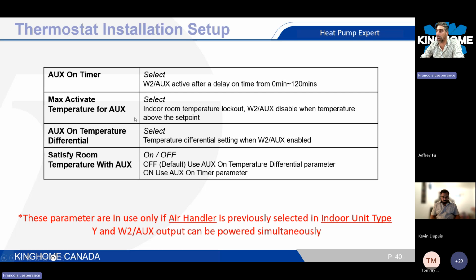Maximum activate temperature for aux. This is an indoor room temperature lockout of aux. So basically, for example, you've set that temperature to 21. If it's more than 21 inside the room, the heat strip doesn't have rights to be powered. So there will be no run for the heat strip if it's over that lockout. Aux on temperature differential is where you set a differential setting from your set point. So for example, if the room temperature is 20, you ask for 22, and you have put a differential of 1 degree Celsius, then you do have permission to power up the heat strip at the same time.